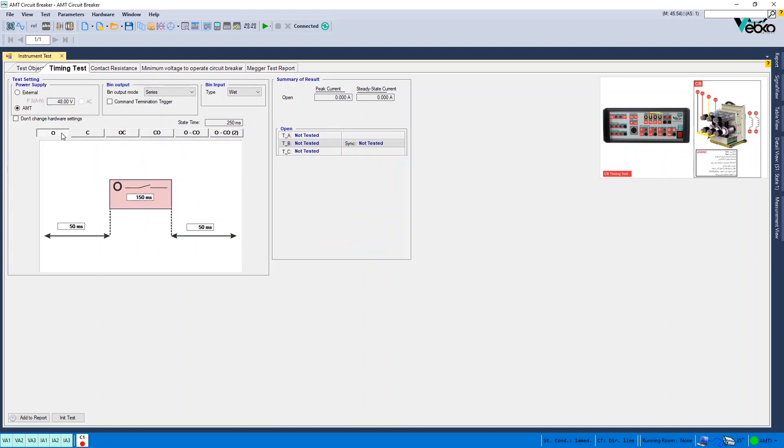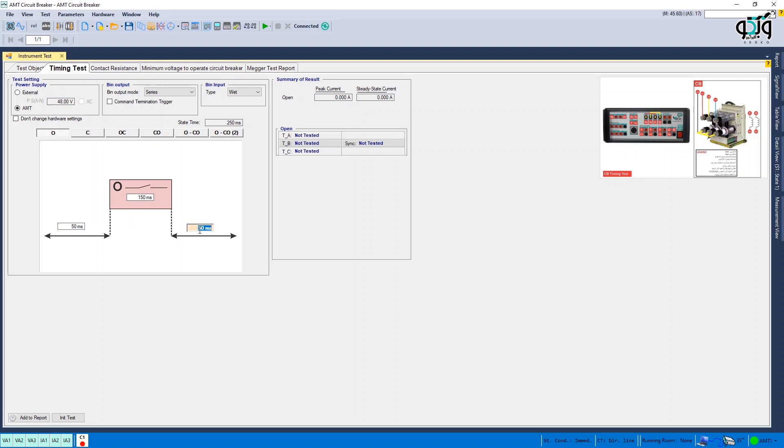For example, in open test, you need to enter three times in the design fields. The first time is related to before command. The second time is related to the duration which the command is kept on the bobbin and the third time is related to after command. In this example, the bobbin is supplied by the device and binary output and binary input are set at series and wet, respectively.